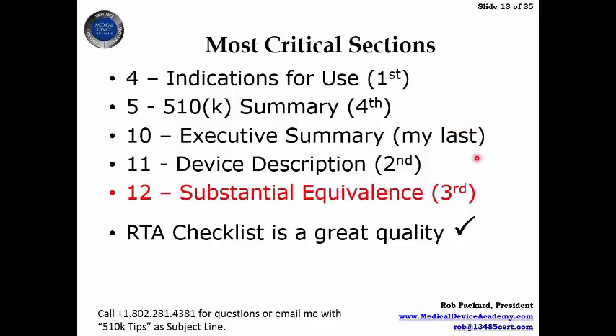The last section I work on is the executive summary. Why is that the last section? It's because I want to have my submission complete. I want to include a lot of key information there, and if you don't include all the models in your submission, you don't indicate what the indications for use are, you don't indicate what your predicate is, if you leave out some of that key information, your executive summary is not going to be satisfactory either. The FDA expects a lot of detail in these sections, so you need to provide that. And once again, RTA checklist. You might want to fill out one of those yourself because it's going to prompt you for some of the things in this device description section that a lot of people routinely forget.